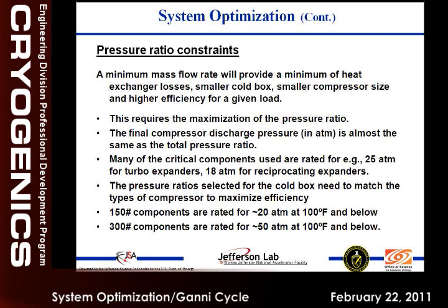Although there is a rating, there is a misnomer in terms of how we practice versus how we rate them in ASME. So you should make sure you are using technical literature: when you say 150 pound components, we normally use them up to 18 atmospheres. That's legally allowed. And 300 pound components up to 50 atmospheres, things like that. Make sure you are using the full range of the machine.